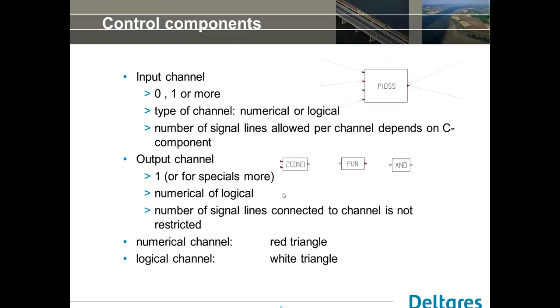Next, we have the control components. The control component has some input channels, and that can be either 0, 1 or more, depending on the component which you have. You also have different types of channels: numerical channels, which can have every value, or logical, which is true or false, or as used in Wanda, 0 or 1. The number of input signals depends on the type of component - for example, if you have a PID, every input channel can only have one input signal. They also have the output channel, which can be one, or for special components it can be more. You can put an infinite amount of signal lines at the output and connect it to as many components as you would like.